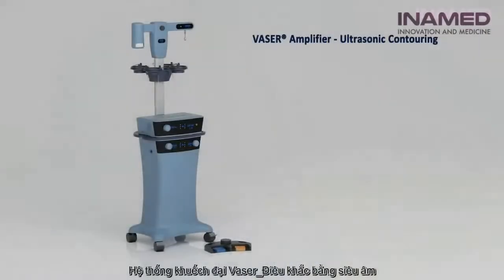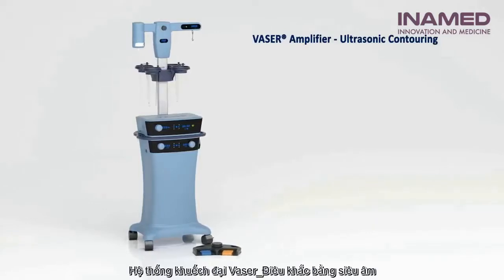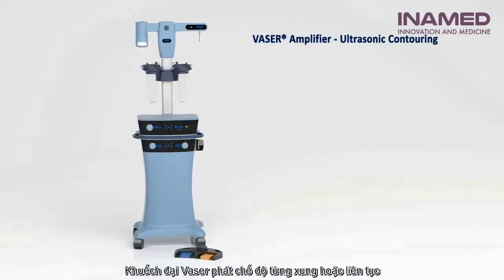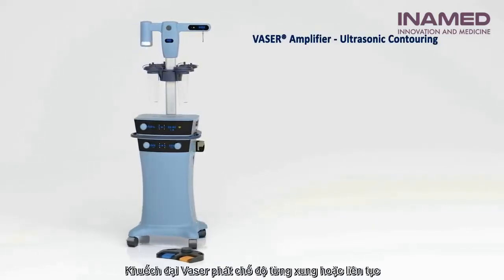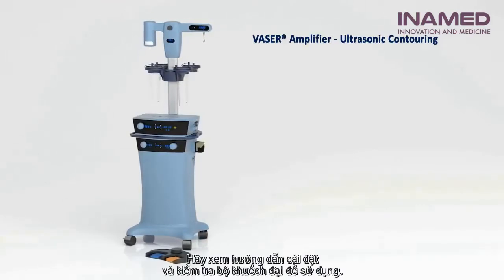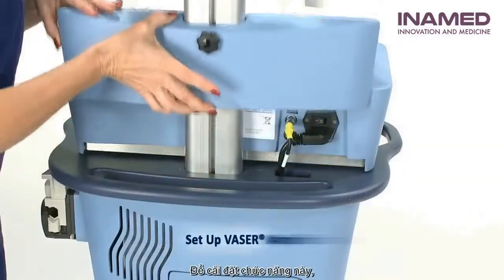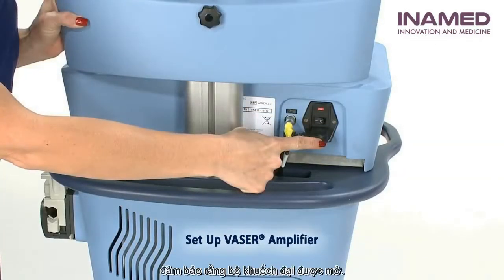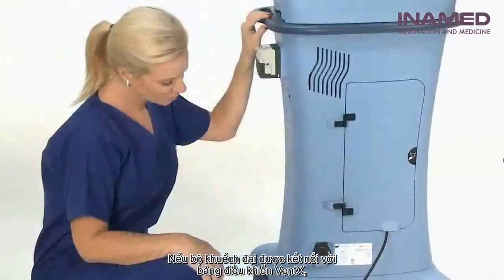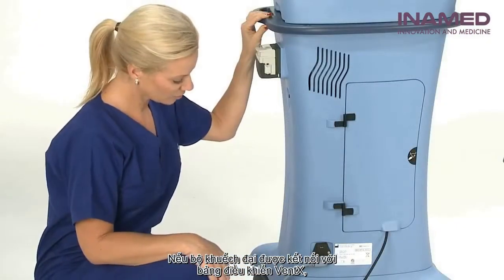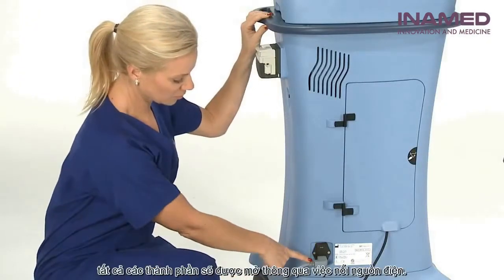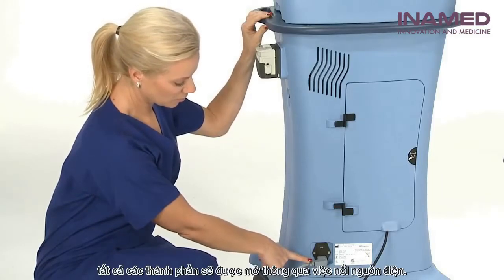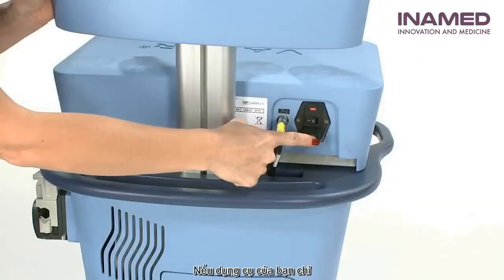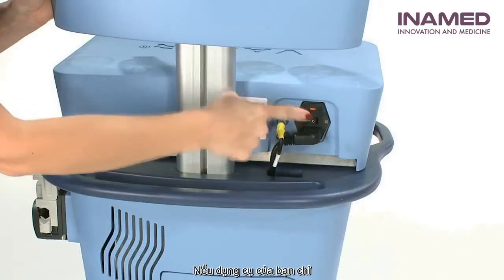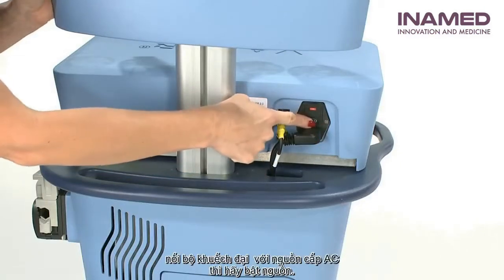Vaser Amplifier Ultrasonic Contouring. The Vaser amplifier emits pulsed or continuous modes of ultrasonic energy to emulsify fat. Let's see how to set up and test the amplifier for use. To set up for ultrasound application, ensure the Vaser amplifier has power. If the Vaser amplifier is used in conjunction with the VentX console, all components are powered through the main power switch.